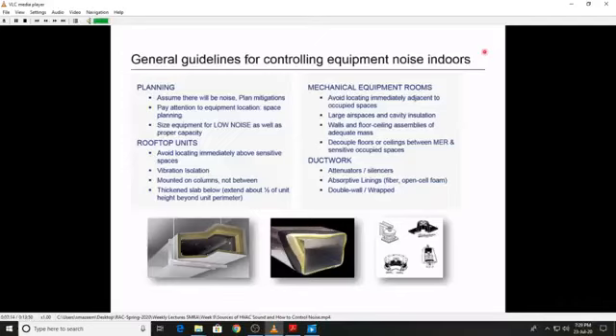And pay a lot of attention to your ductwork. Be sure to use attenuators and silencers if they're necessary. Plan on using absorptive linings for at least a fair amount of the main duct path. And then if you have breakout noise issues because of thinner gauge ductwork, there are many products available that allow you to wrap the ductwork and absorb and block the sound.